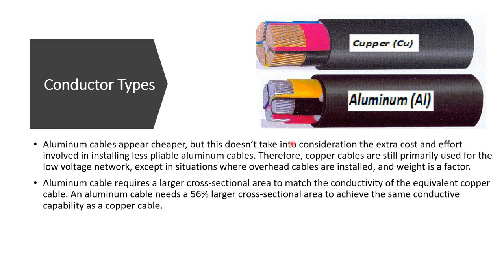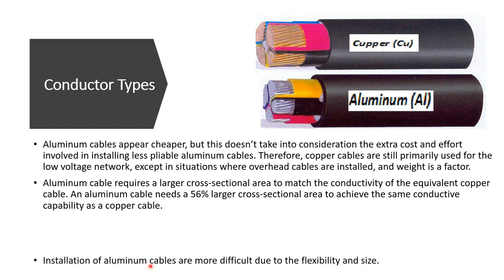To carry the same current as copper, aluminum requires a larger cross-sectional area — approximately 56% larger — to match the conductivity of the equivalent copper cable. For example, if 50 amperes are needed, the aluminum conductor must have a much higher cross-sectional area than the copper equivalent. This also makes aluminum cables more difficult to install due to their size and reduced flexibility.